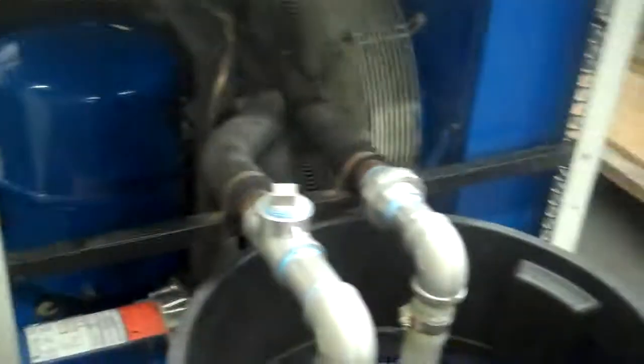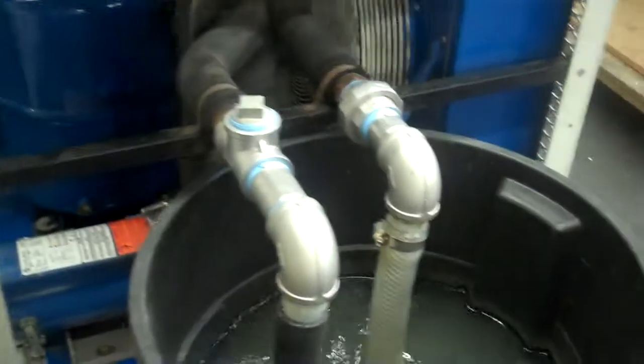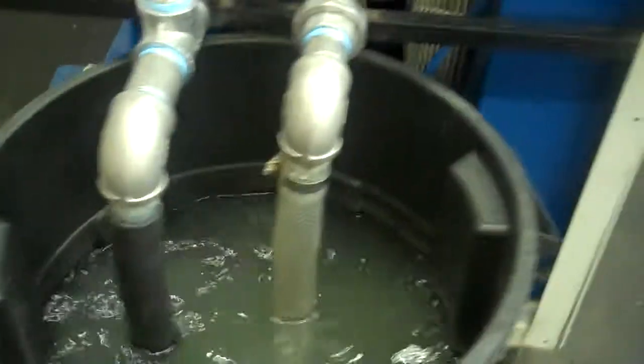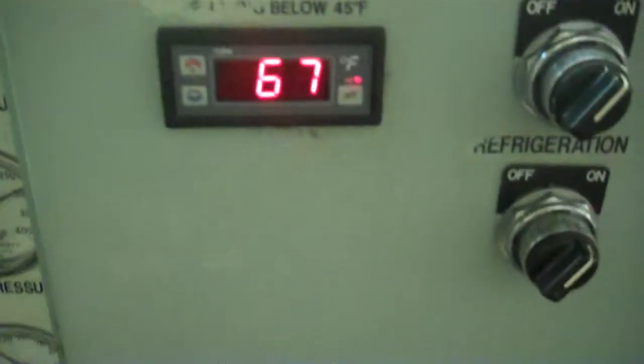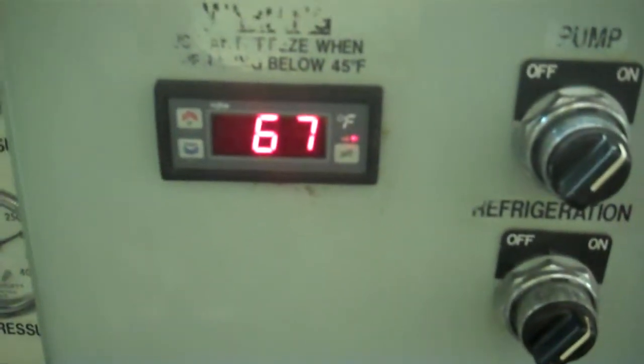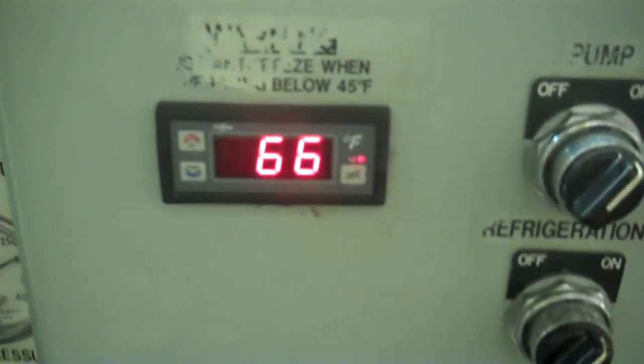This is the other cover here, which would go on this side, and here is the end panel, which would go right here. We painted that after we put on these connections for our test. That's why that cover's not on. It's kind of nice to see the inside, because it is a really clean, solid unit. So we'll come back to video number 2 in a second as we approach our set point. But as you can see, we've already gone from that 85 or 87 down to 66 right now.